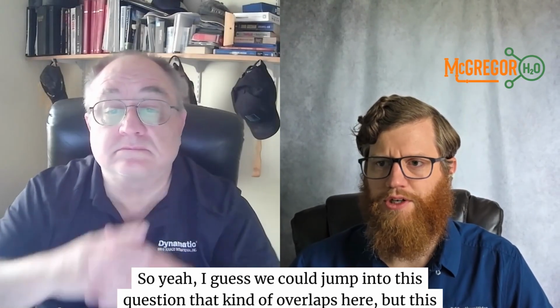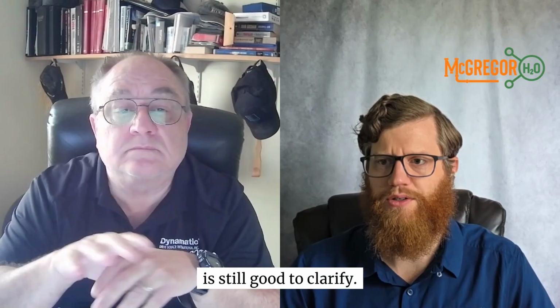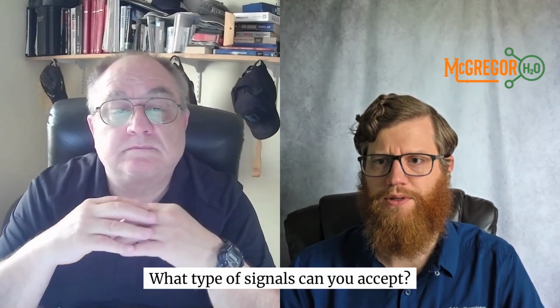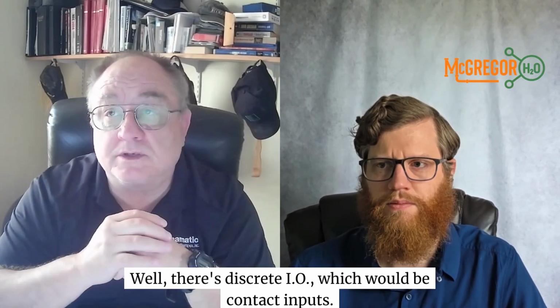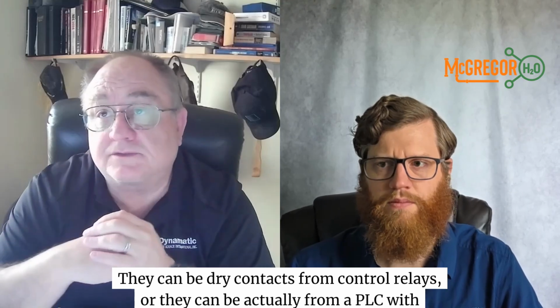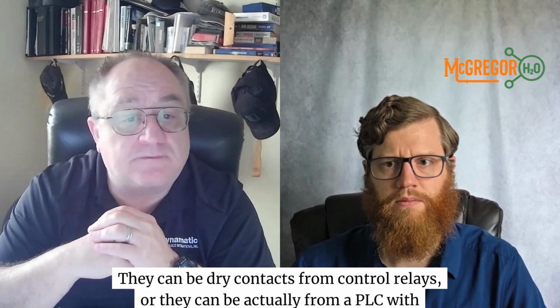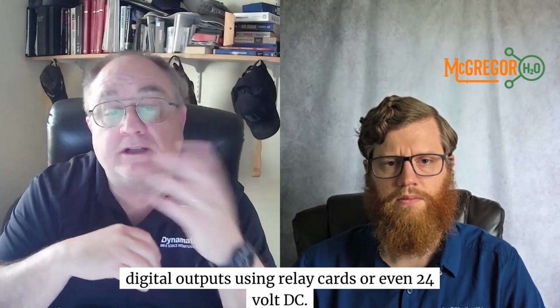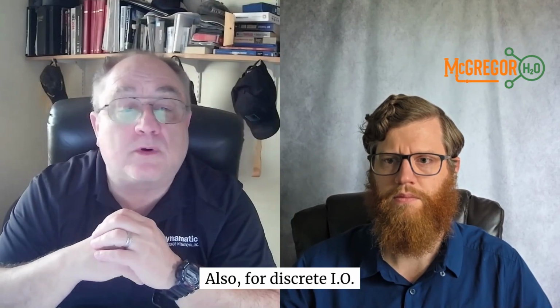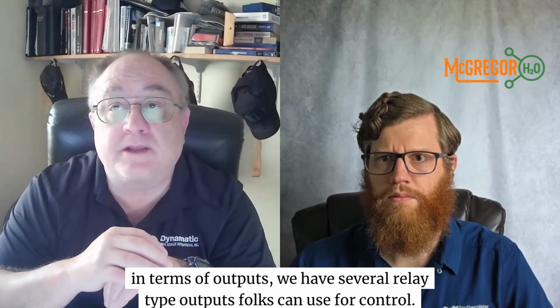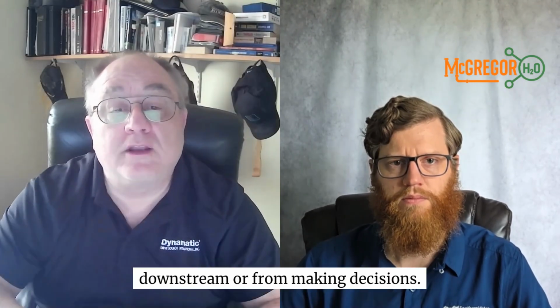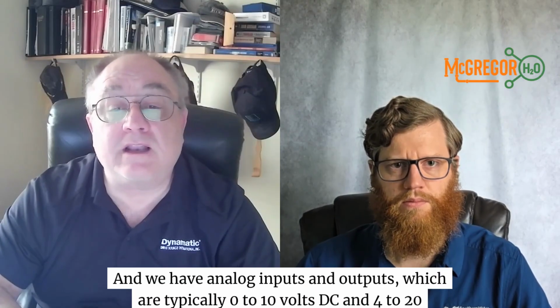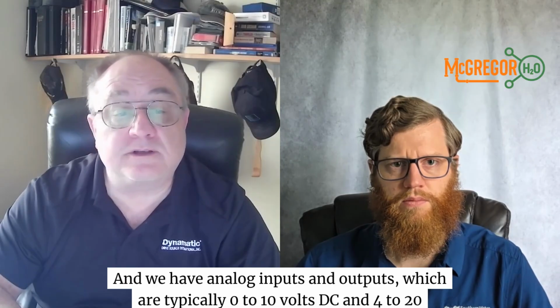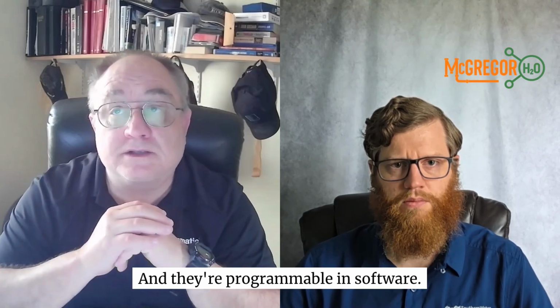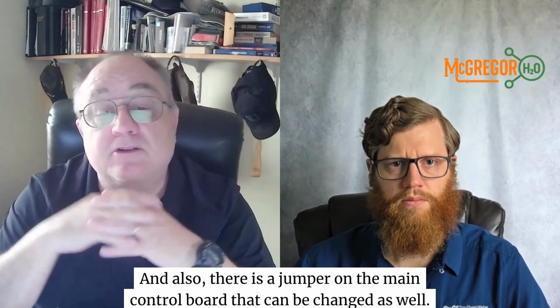So yeah, I guess we could jump into this question that kind of overlaps here, but it's still good to clarify. What type of signals can the drive accept? Well, there's discrete I/O, which would be contact inputs. They can be dry contacts from control relays, or they can be from a PLC with digital outputs using relay cards or even 24-volt DC. Also, for discrete I/O in terms of outputs, we have several relay type outputs folks can use for control downstream or for making decisions. And we have analog inputs and outputs, which are typically 0 to 10 volts DC and 4 to 20 milliamps. And they're programmable in software. And also there's a jumper on the main control board that can be changed as well.